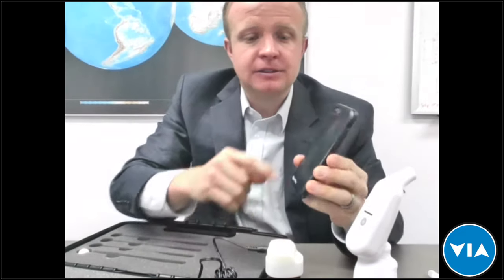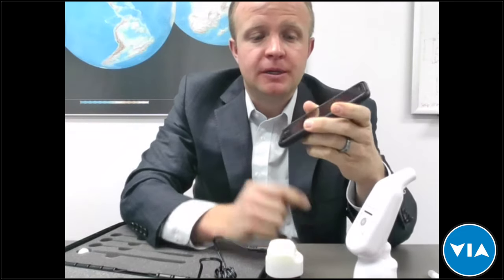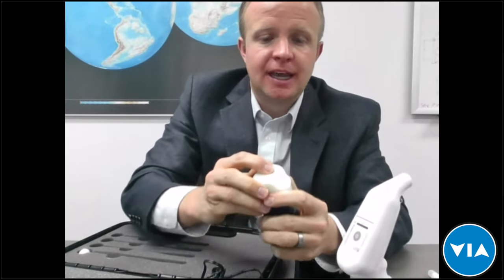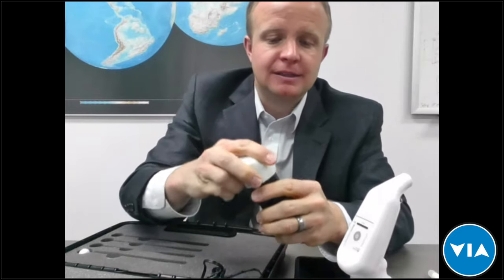The reason we've designed it this way relates to IATA — the International Air Transport Association — regulations about shipping lithium-ion batteries. There is an exception to that rule, just like your cell phone, if the battery is contained inside the device. We ship our thermal coagulator with the battery inside the device, as well as the examination light, so we fully meet that exception and have no conflict with international regulations for lithium-ion batteries.